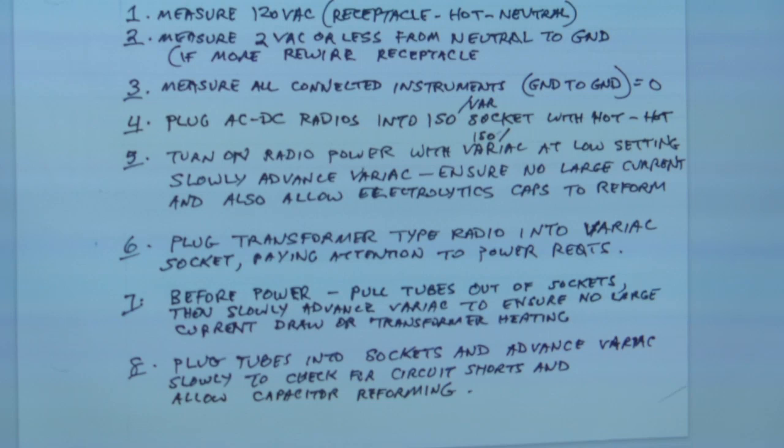The reason why this test is important too, as I was mentioning to Greg, we were having a little discussion before the session, is that occasionally you're going to have transformer problems that only show up when the power is applied. And even at certain voltages, you can fire up a transformer, and this has happened to me, and at full rated voltage, it will break down occasionally.